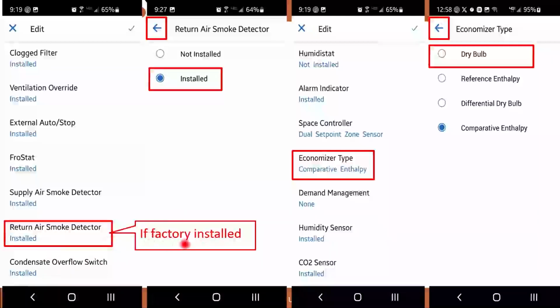Return air smoke if factory installed. Again, that's if factory installed. If you have the ducted existing duct smoke detector, you're going to wire it into J18. So you will not have this, you'd say not installed. We're going to wire it into the e-stop. Economizer type, once you turn on fresh air or outside air, it'll give you economizer type. We're going to change that to dry bulb unless you have it ordered for comparative enthalpy.